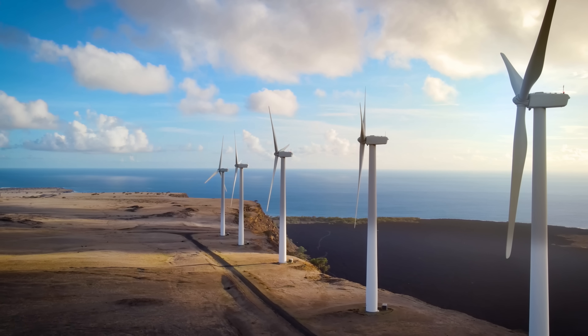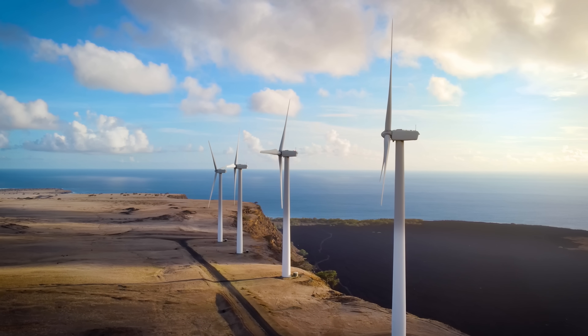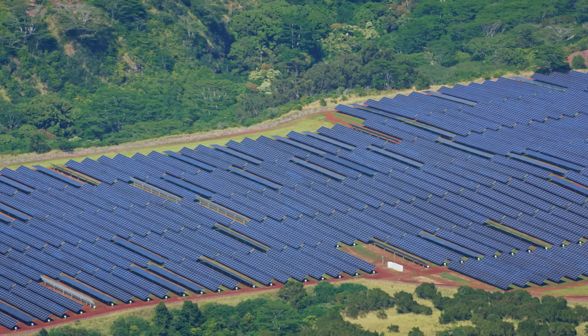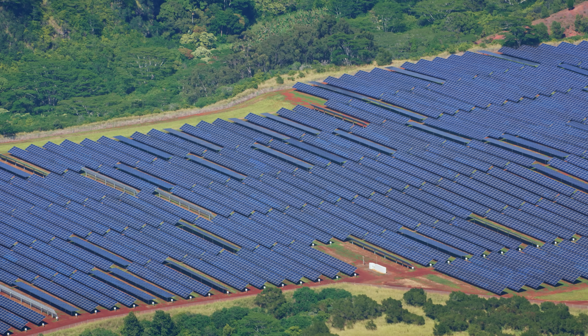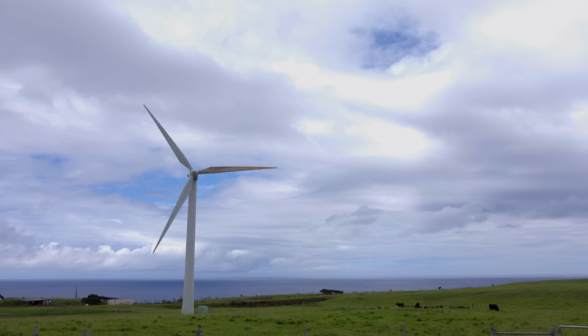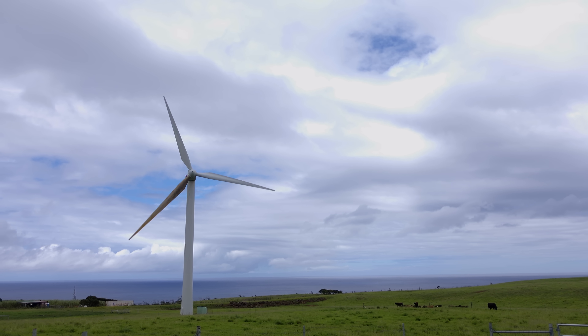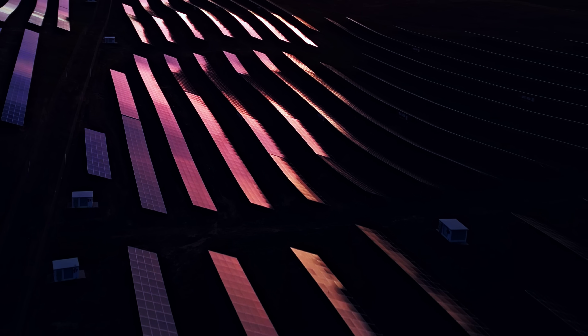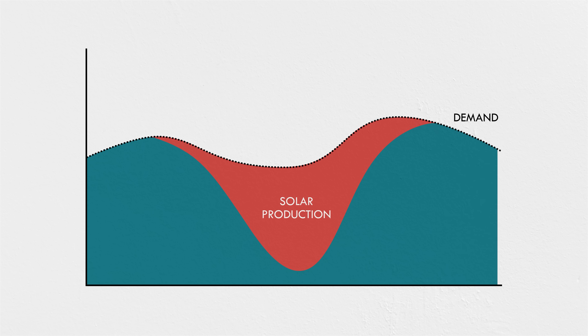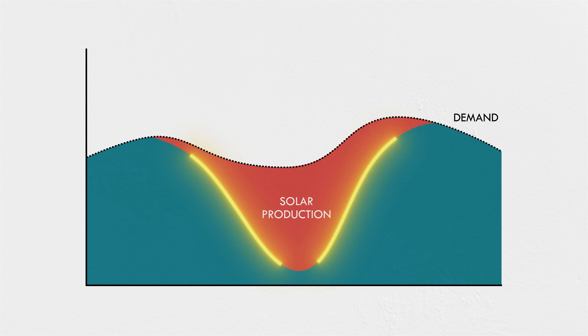But it's not just that the grids are small. The bulk of the remaining roughly 25% of Hawaii's electric power not produced in oil-fired power plants comes from renewable sources — wind, solar, and a single geothermal plant. This reduces CO2 emissions and the state's exposure to fuel supply chain complexity and price volatility, taking advantage of resources actually available on the islands. But renewable sources come with their own engineering challenges, particularly when they represent such a large percentage of the energy portfolio. Renewable sources are intermittent — you don't get power when the wind doesn't blow or the sun doesn't shine. That sporadic nature necessitates storage or firm baseload to make up the difference, and requires those backup facilities to ramp down and up very quickly as the sun and wind come and go.